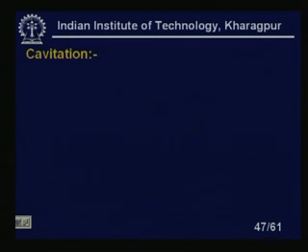Cavitation, we have talked about cavitation so much. What is this cavitation? Let us look at it in detail, because this is very important. You must stop the cavitation, otherwise erosion will start and the valve calibrations, whatever typical flow characteristics you have desired, you may not get, ultimately leading to poor product quality. So, those things are very important. You must study the cavitation details, and we have to stop the cavitation inside the valve.